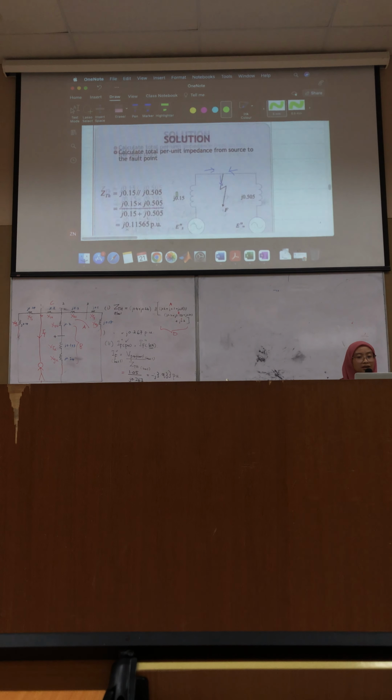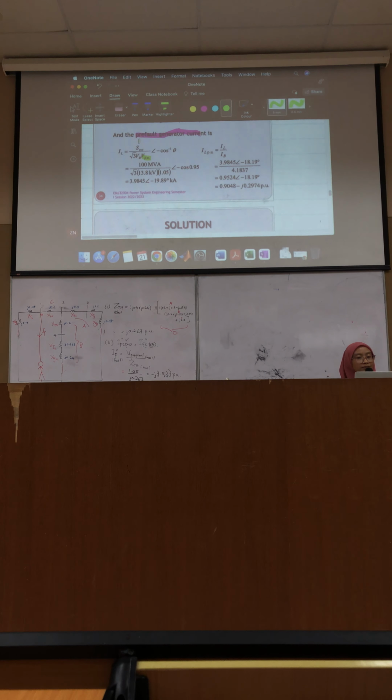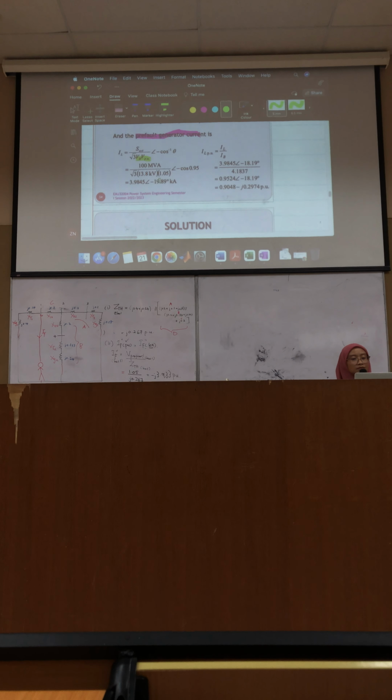Now, what happened here is actually dia cuma nak kira 14.49 lah. Dia nak tadi 5% above the, sebab the pre-fault. Okay, pre-fault current, you kena ambil kira V pre-fault lah. Actually this one adalah V pre-fault. VB kali dengan VPU. Ataupun you nak buat asing pun boleh, you nak buat V pre-fault equal to 1.05 times 13.8, 14.49. Ataupun you nak straight letak dalam ni pun boleh. Tak ada masalah. Okay, so that the IL ni is actually the pre-fault current of the generator.